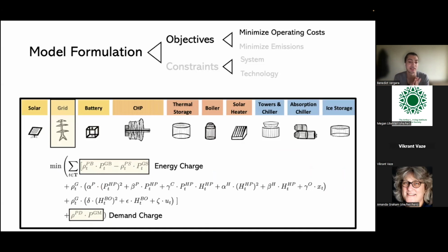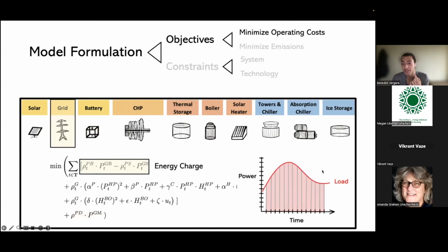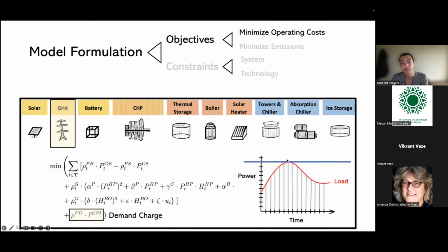These are two different ways of charging, typical for cities and really any power utility serving larger buildings, because they need to penalize you for pulling a lot and then not pulling. So having an energy charge and a demand charge is a typical way of modeling the costs. The area under the power and time curve is your energy charge, and the peak point you're pulling is your demand charge.